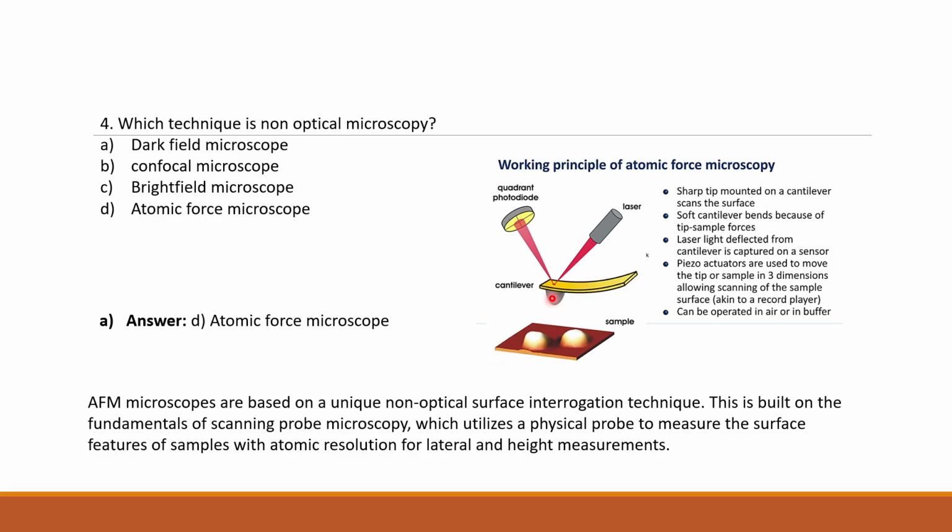Okay, so here you can see this one. This is your probe they were talking about. This is your physical probe, which is a sharp pointed tip. But it is also flexible. So you should remember, when it has to probe and move across the sample, it has to be flexible. If it's sharp and rigid, it will break, and then there is no point in moving it. This cantilever is movable, and your sample stage is also movable. So you will get a full area scanning.